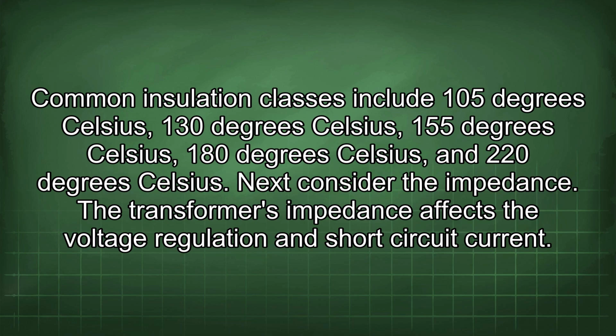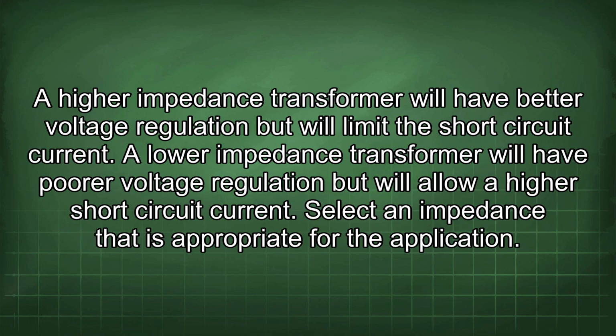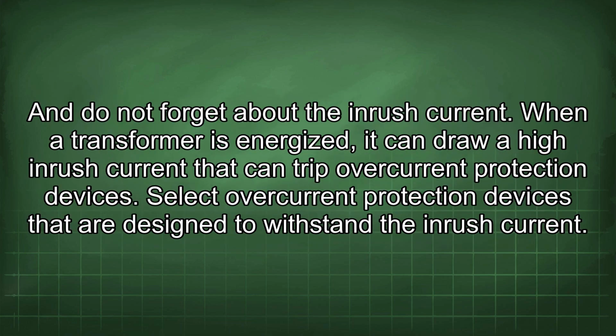Next, consider the impedance. The transformer's impedance affects the voltage regulation and short-circuit current. A higher impedance transformer will have better voltage regulation but will limit the short-circuit current. A lower impedance transformer will have poor voltage regulation but will allow a higher short-circuit current. Select an impedance that is appropriate for the application. And do not forget about the inrush current. When a transformer is energized, it can draw a high inrush current that can trip overcurrent protection devices. Select overcurrent protection devices that are designed to withstand the inrush current.